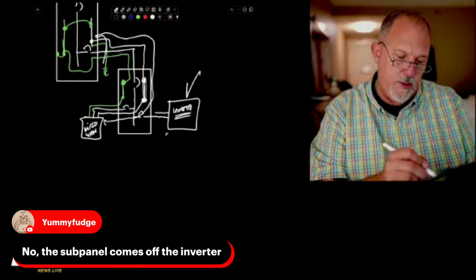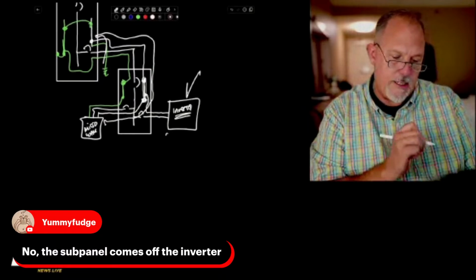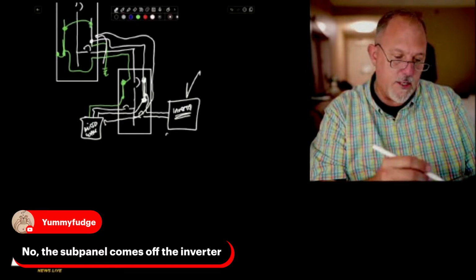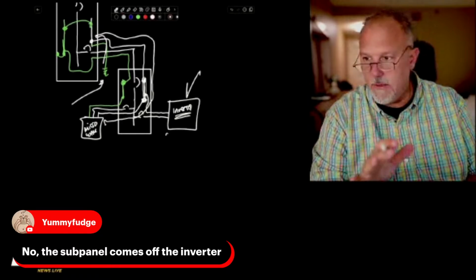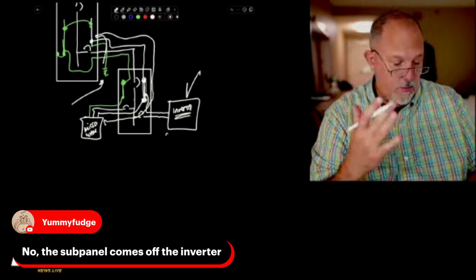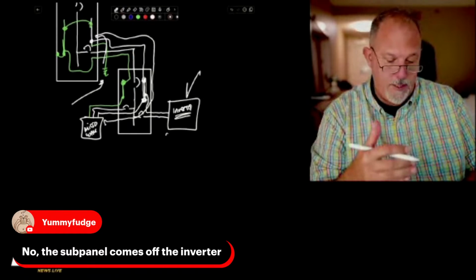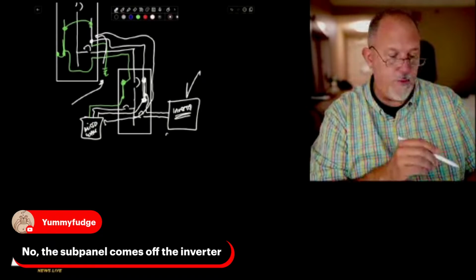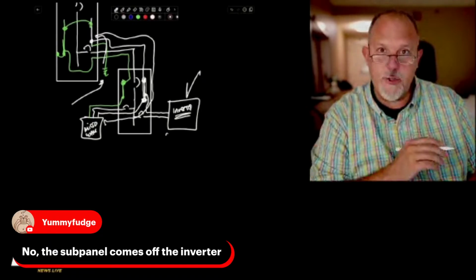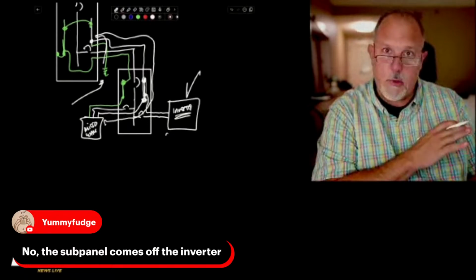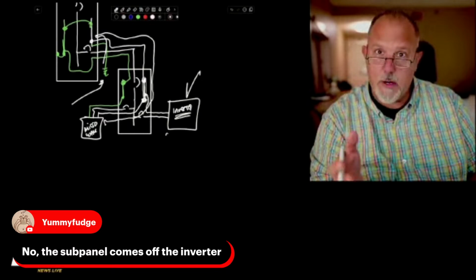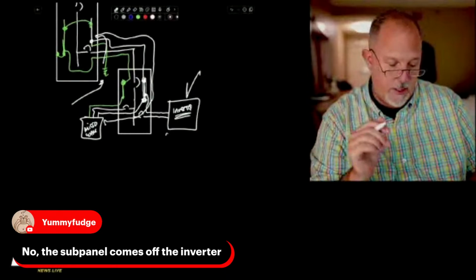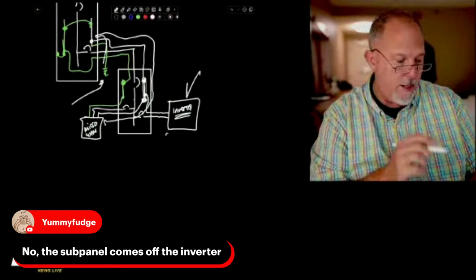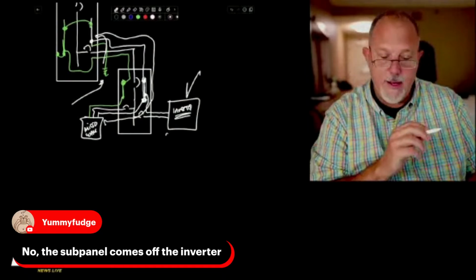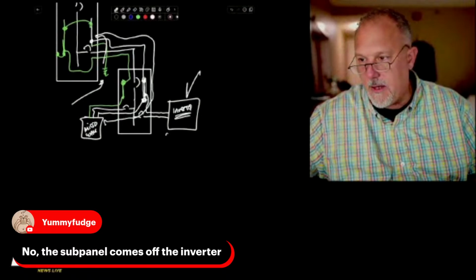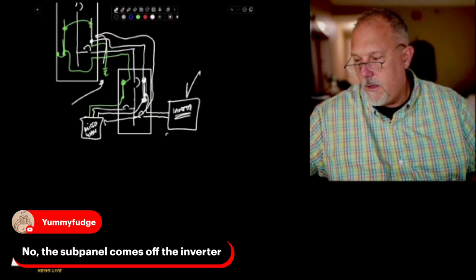So, what I'm not showing here is this. You would have a hot and a neutral, right? So the neutral has to land there. And because all of that neutral is all bonded back to that location, I think, well, yeah, you're grounded. The inverter is grounded. The neutral is grounded through the service panel board because that neutral is the grounded conductor, and it's grounded at one point in the service equipment, which is required by code. You can't bond those anywhere else in the system. They're all insulated from each other outside of that one connection at the service panel. So I think that's how I would approach that.